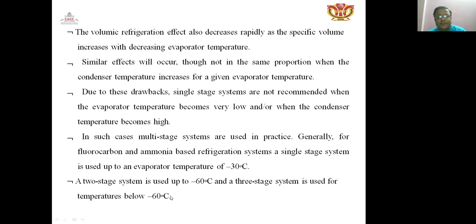Apart from high temperature lift applications, multi-stage systems are also used in applications requiring refrigeration at different temperatures. For example, in dairy plant refrigeration, we will require minus 30 degrees for making ice cream and 2 degrees centigrade for chilling milk. In such a case, it is advantageous to use a multi-evaporator system with the low temperature evaporator operating at minus 30 and the high temperature evaporator operating at 2 degrees centigrade.